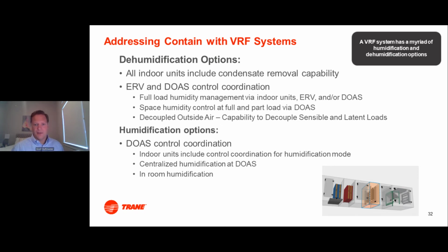If we're looking at adding humidification, that becomes now a new challenge. Traditional systems with a unit per classroom, you could be looking at distributing many different humidifiers throughout a space, which can become obviously expensive and hard to manage. With the DOAS unit being centrally located, now if you need to add humidification mode for a VRF design with some of this latest guidance, you can do that in fewer locations centrally located at your DOAS unit. Again, most of the time you'll only need to add humidity when the outside air and the conditions are requiring that. Being able to do that centrally can be a big cost saver. Prevents you from needing to do things like in-room humidification, which is again part of the guidance, but can be expensive to do.